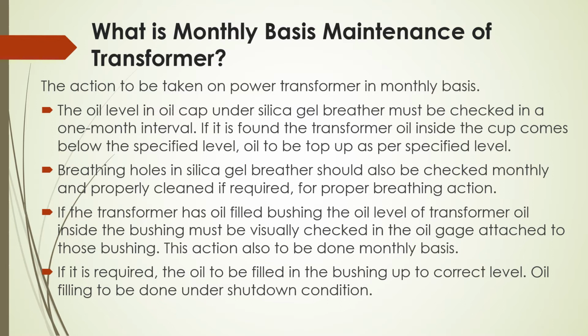Breathing holes in the silica gel breather should also be checked monthly and properly cleaned if required for proper breathing action. If the transformer has an oil filled bushing, the oil level of the transformer oil inside the bushing must be visually checked in the oil gauge attached to those bushings. This action is also to be done on a monthly basis. If oil is required to be filled in the bushing up to the correct level, oil filling is to be done under shutdown condition.